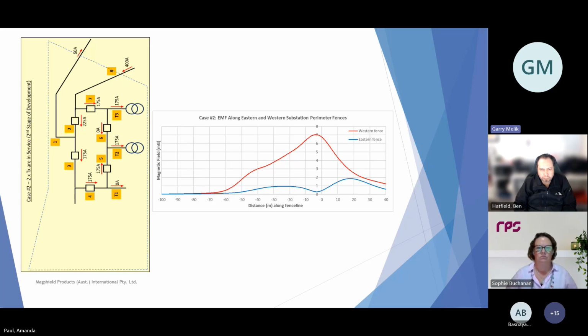The EMF profile calculated from the three-dimensional model shows that the highest field along the western perimeter fence will be just under 7 milligauss, while the highest field along the eastern perimeter fence slightly increases to under 2 milligauss. The shape of this profile is slightly different because the substation will have a second transformer, and the current distribution through the system of bus bars will differ slightly.